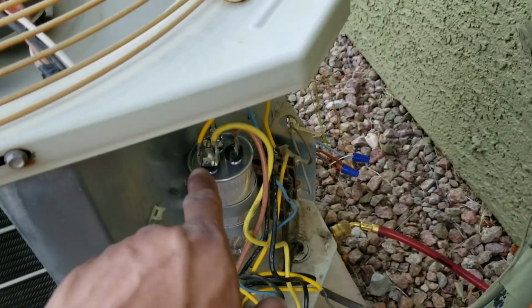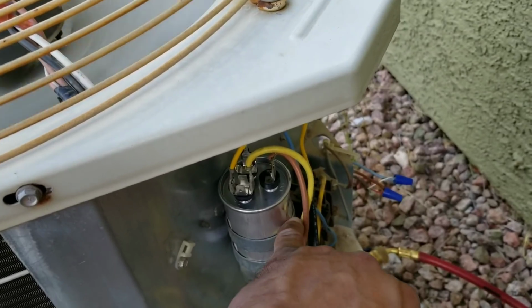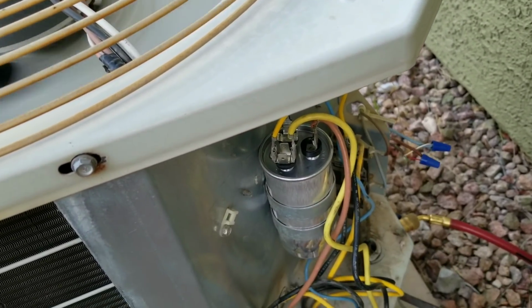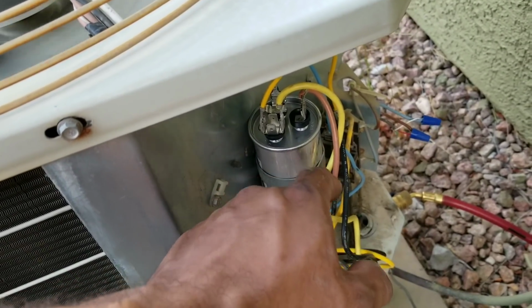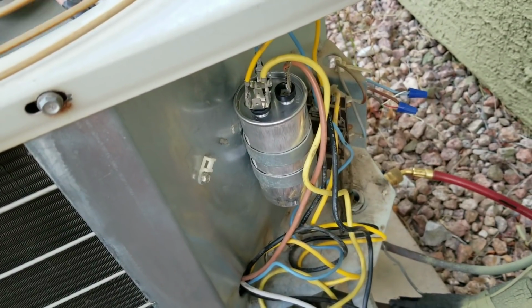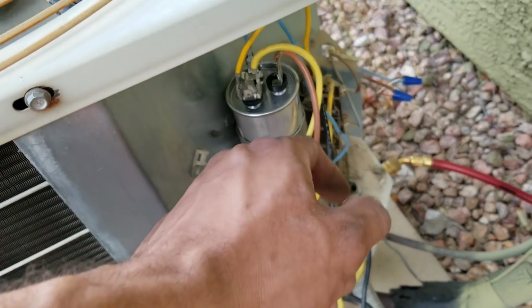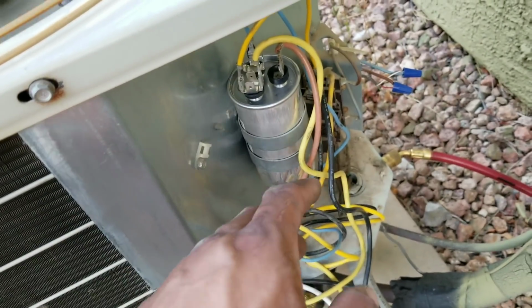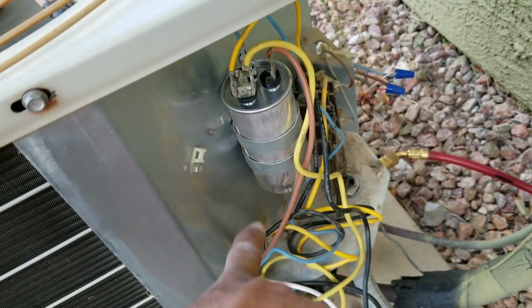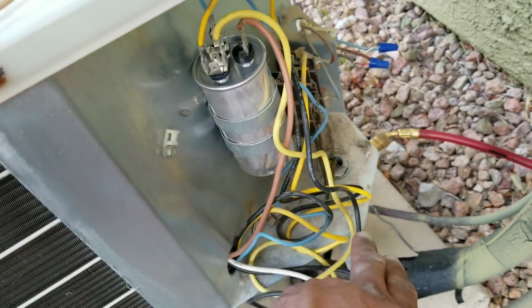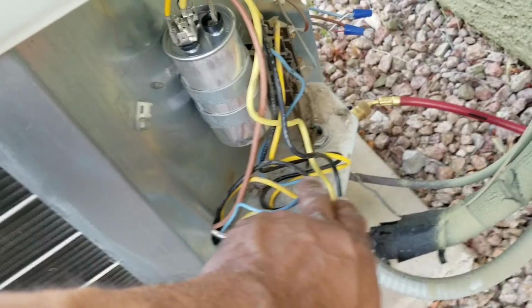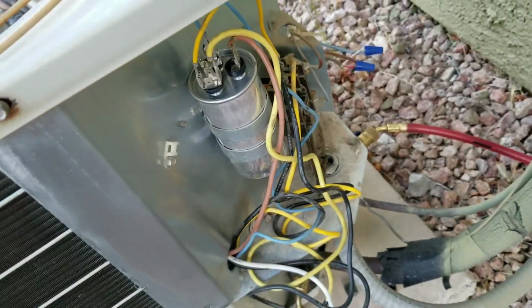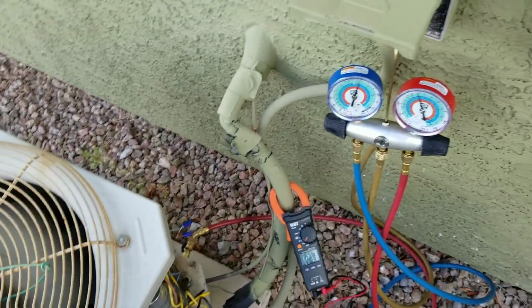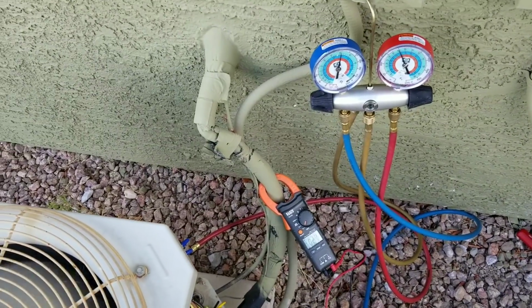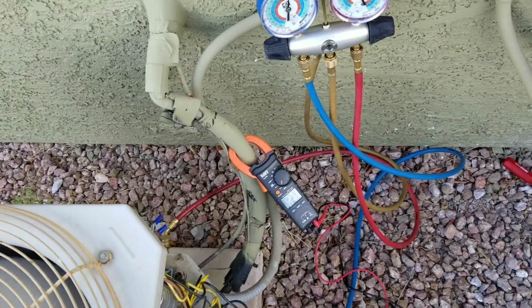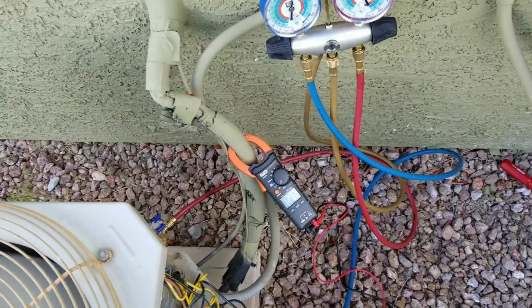This is a dual capacitor, and you can see here the brown wire that's coming in, that's for your fan. Sometimes the capacitor fails. Your compressor will still run, but your fan motor won't, so you have to replace the capacitor. Or you may have two separate capacitors. You may have one capacitor up top, you may have one capacitor sitting in the box somewhere down here or somewhere up there. So basically the whole situation is based on what the problem is initially when you encounter an AC call.